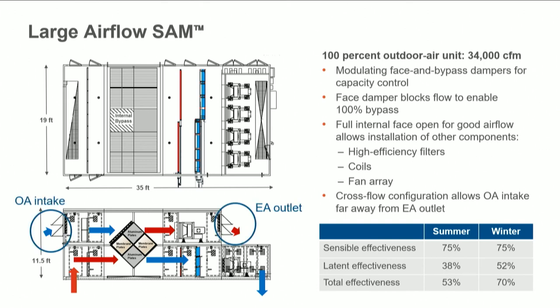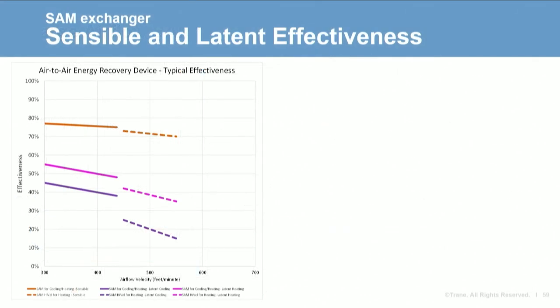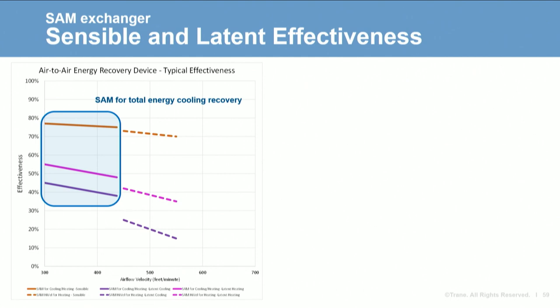SAM used for cooling recovery, with a target of 50% total effectiveness, will be used at a similar air handler face velocity as a membrane exchanger — 300 to 400 feet per minute for optimum performance versus footprint required. SAM will have a sensible effectiveness of 72 to 77%, with a latent effectiveness in summer of 38 to 45%, for a total effectiveness of 50 to 54% during summer peak cooling. Total effectiveness during winter heating will be in the range of 68% to 72%.